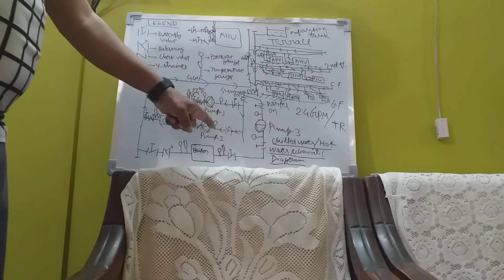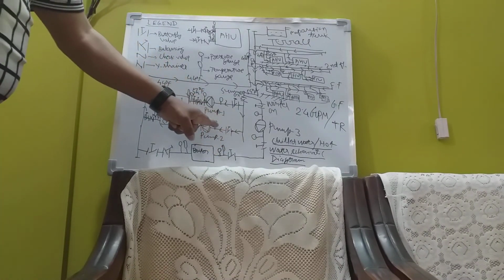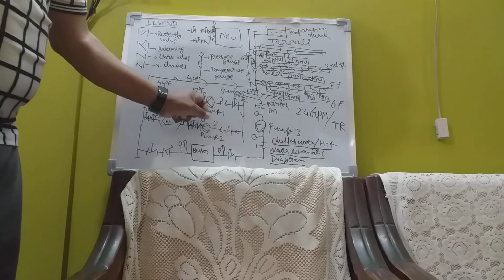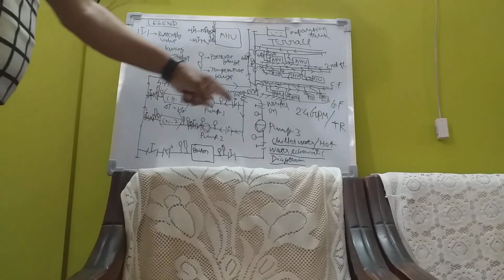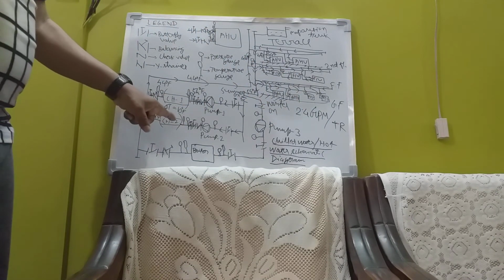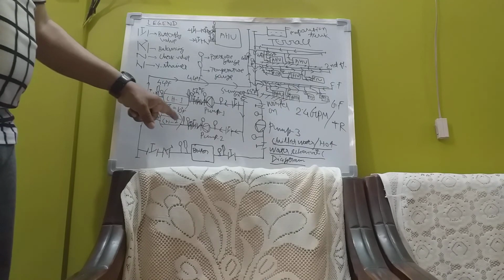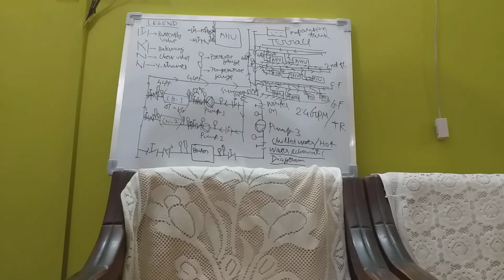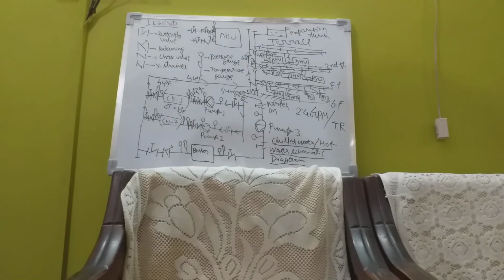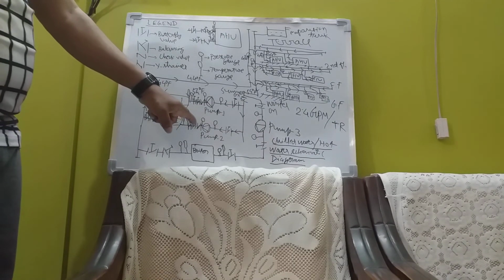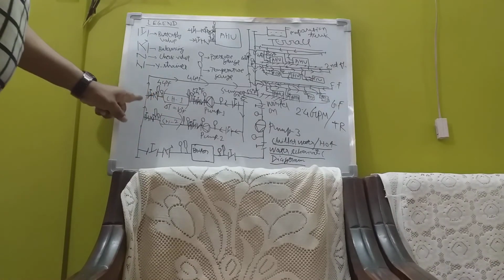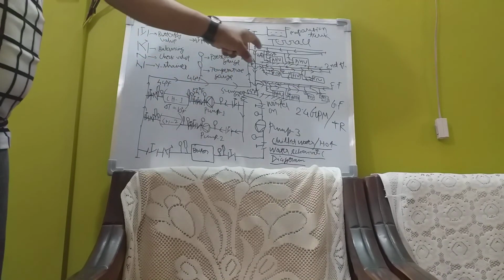In case of the chilled water pipeline, the main pipe holds the highest amount of gallons per minute. The gallons per minute is determined by 2.4 GPM per ton. If it is a 100 ton machine, then 240 GPM is passing through this. Then this pipe will be designed at 240 GPM. For 240 GPM, the corresponding diameter will be seen through a chilled water pipe chart, and accordingly the diameter will be determined. And then it goes like that and supplies to the AHUs again.